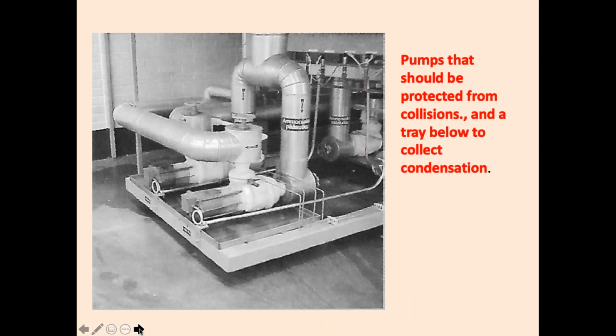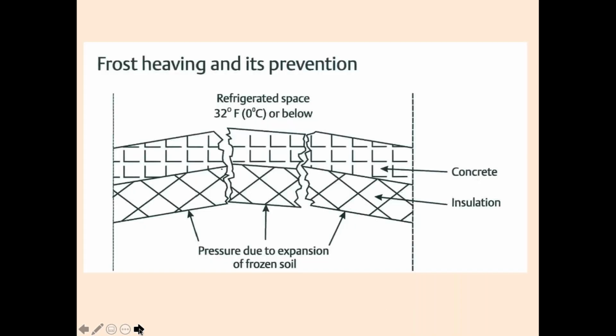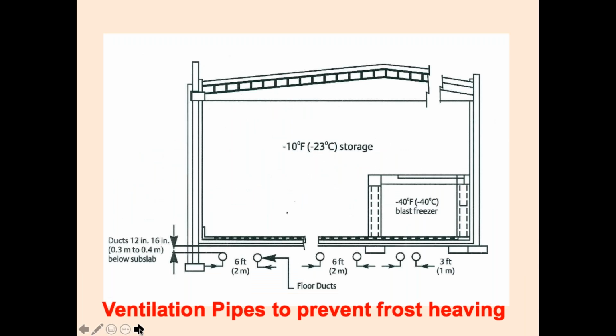For pumps, provide a tray below so that condensation and pump dripping does not get spread all along the plant room. It collects in the tray. The flooring of the plant room, machine room, is important. There is frost heaving. What happens is this moisture which goes onto the machine room floor seeps through the cracks, and when the temperature is lowered, the water expands and the floor cracks. To avoid this, provide these ventilation pipes to prevent frost heaving. There are 3-4 methods of providing this anti-heaving solution, like glycol, heating elements, these ventilation pipes, etc.